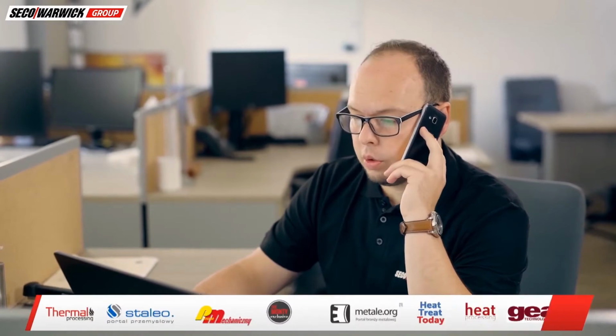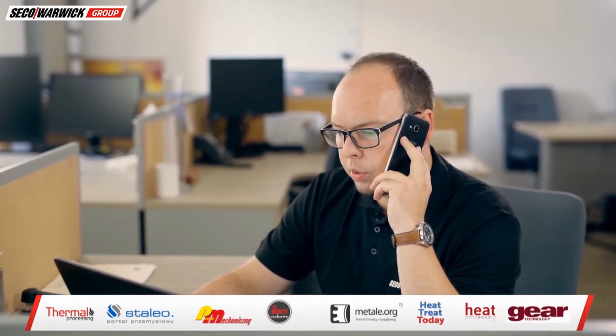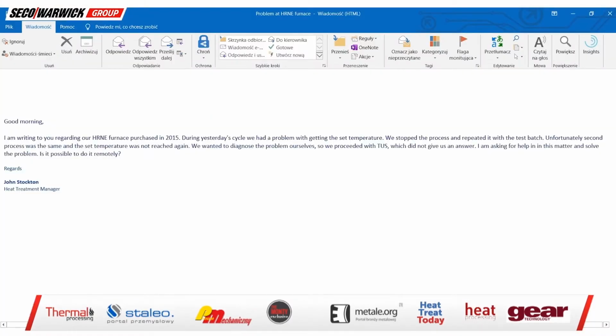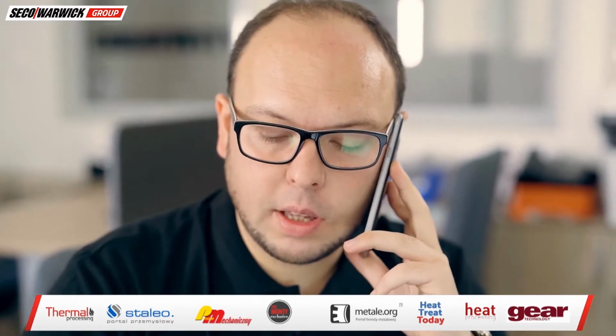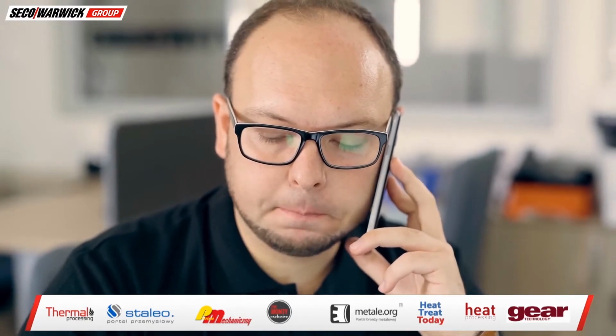Hello, good morning. It's SECO WARWICK services. I just got your email about the problem with the furnaces, so I would like to get some additional information. Okay, so can you tell me what is the number of this furnace? You can find it on the nameplate on the furnace or in the electrical cabinet. Okay, so I have the information that you had a problem reaching the set point during this cycle yesterday. Can you tell me if there were any alarms? Okay, no alarms during the cycle. And did you have any changes on this furnace lately? Thermocouple or anything else?